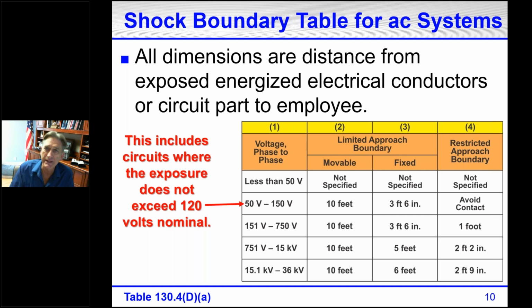Well, the footnote has to be in there because the title above column 1 says voltages measured phase to phase. Well, when we're measuring voltage in a 120 volt circuit, we're not measuring phase to phase, unless it is a certain type of 120 volt system that might be used in a recording or TV studio. Then it could be measured phase to phase, but normally no. 120 volts is measured phase to ground or phase to neutral.